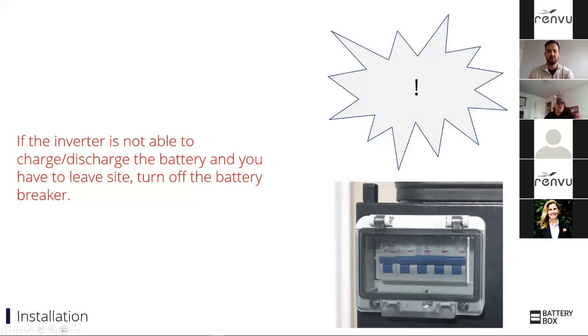So the long story is, what we recommend is, if you're at site doing an install and you're not at the point where the installation's finished, just turn off the battery before you leave site. When you come back, you can turn it on and you'll have hours of time to work before it needs to be communicating and able to charge. Don't want to scare anyone, but it can save you time if you don't have to send an external DC charger to charge things up. That's usually always avoided even in these situations, but it's just best practice to always turn off the battery before you leave site.